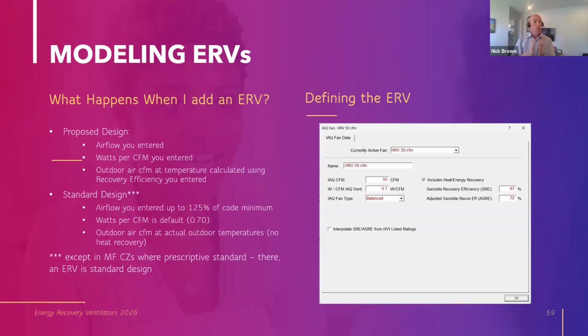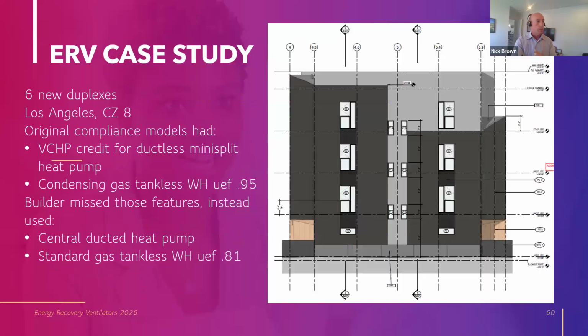Watts per CFM will be modeled at default. So if you have a system better than 0.7 watts per CFM, your compliance benefits. And it's going to assume no heat recovery. That assumes we're not in one of those 8 multifamily climate zones where heat recovery is prescriptive standard. In that case, it will have that heat recovery. I'll give you a case study, and then I'll pause for questions before handing it back to Scott.